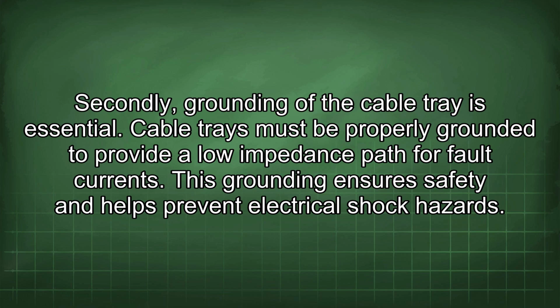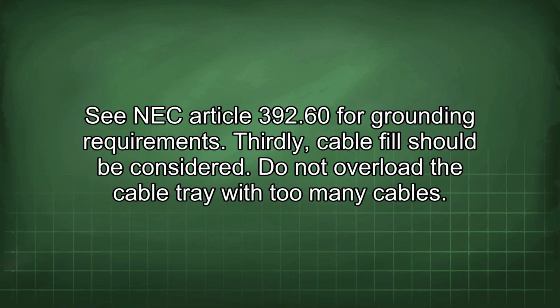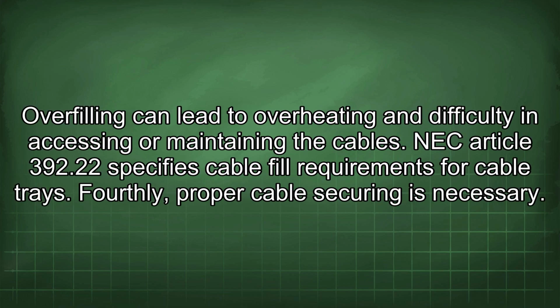Cable trays must be properly grounded to provide a low impedance path for fault currents. This grounding ensures safety and helps prevent electrical shock hazards. See NEC Article 392.60 for grounding requirements. Thirdly, cable fill should be considered. Do not overload the cable tray with too many cables. Overfilling can lead to overheating and difficulty in accessing or maintaining the cables. NEC Article 392.22 specifies cable fill requirements for cable trays.